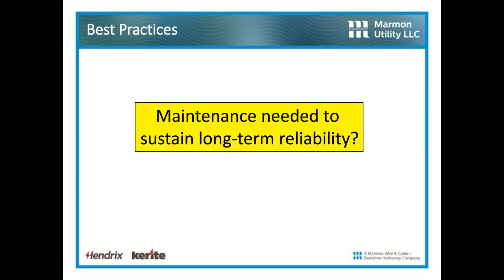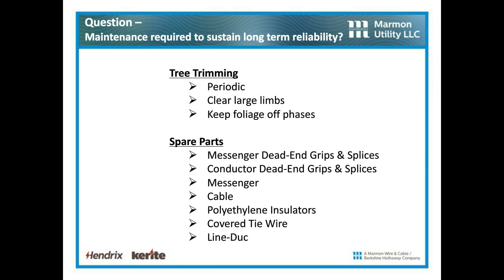How about maintenance? What do I need for long-term reliability? A little bit of periodic tree trimming. Keep the large limbs off the trees, keep the foliage off the phases, and keep a couple of spare parts: messenger, conductor, grips, splices, cable, insulators, covered tie wire, and Line-Duc.